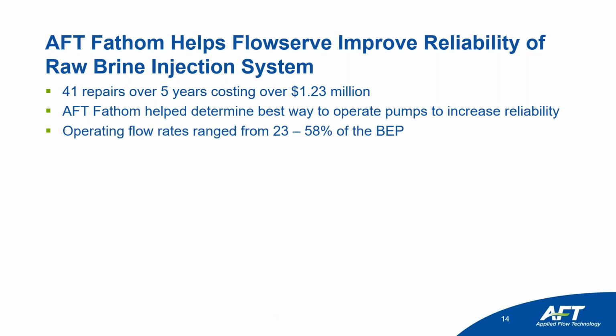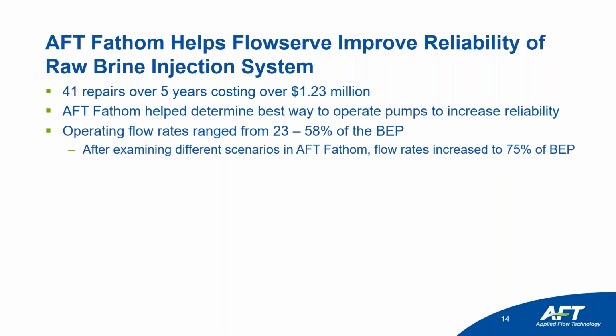They found ways to operate their pumps a lot better by simply closing off pumps that were not needed. Again, you're not going to have to do huge magical modifications to your system in order to get it to operate better or to be more efficient. It's simply a matter of maybe turning off a few pumps and motors that don't need to be operating, and it'll dramatically increase your energy savings and avoid your operational problems. So now that their pumps are operating at 75% of best efficiency point, they're not going to have this problem very much anymore. It's going to dramatically reduce those costs, increase the profitability of their system.